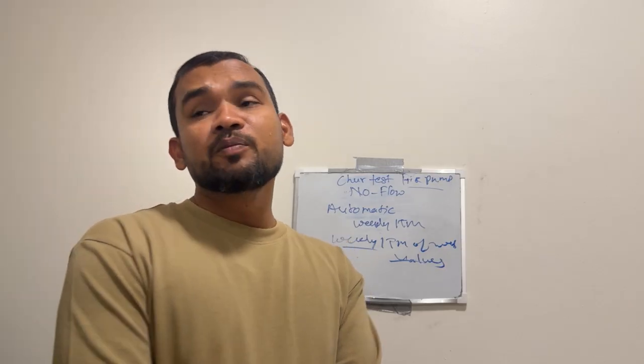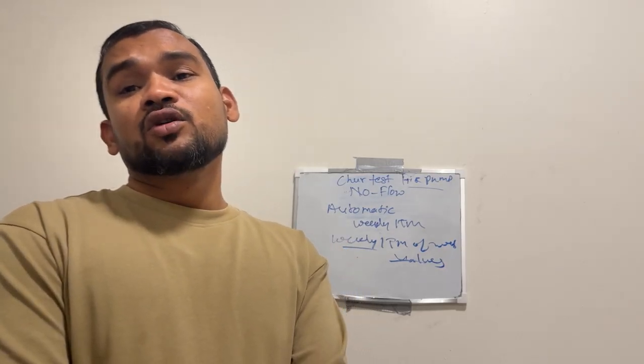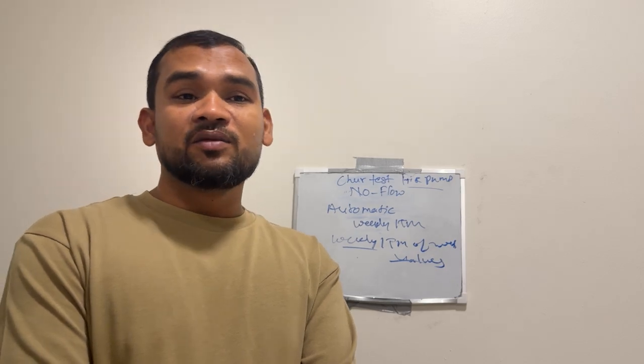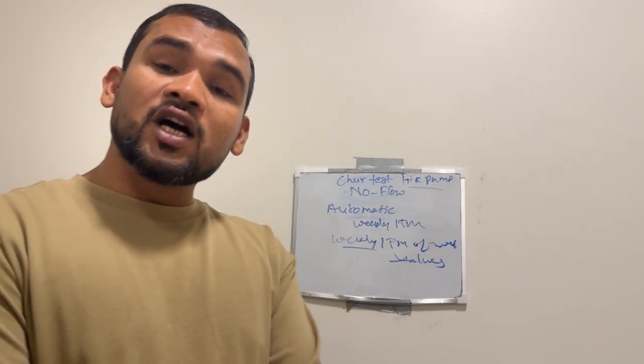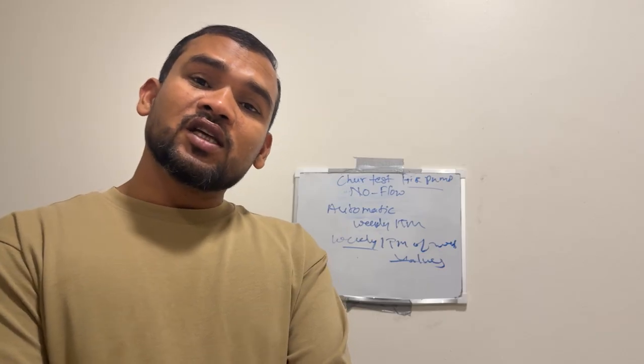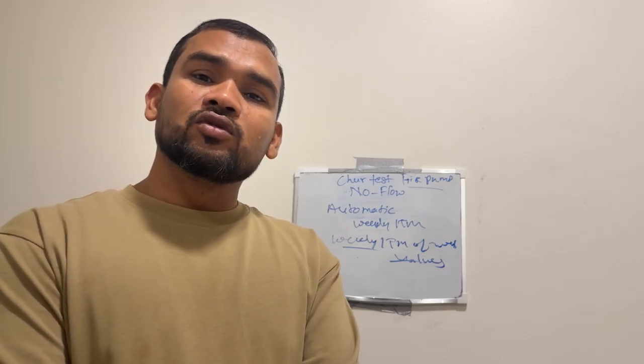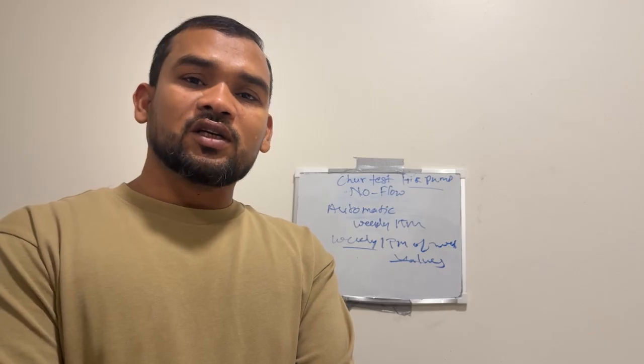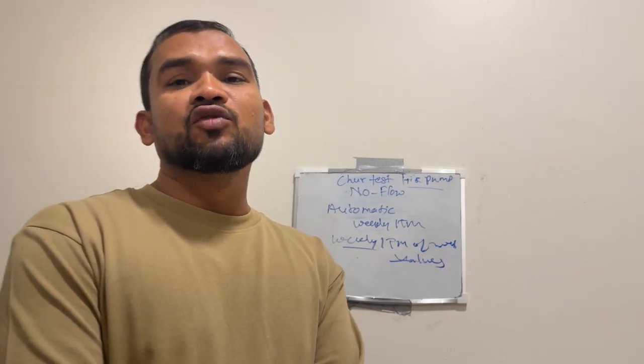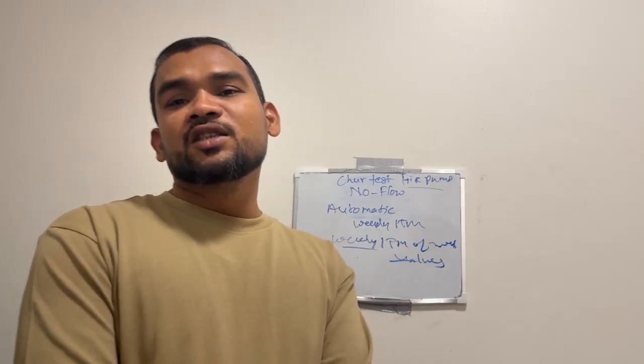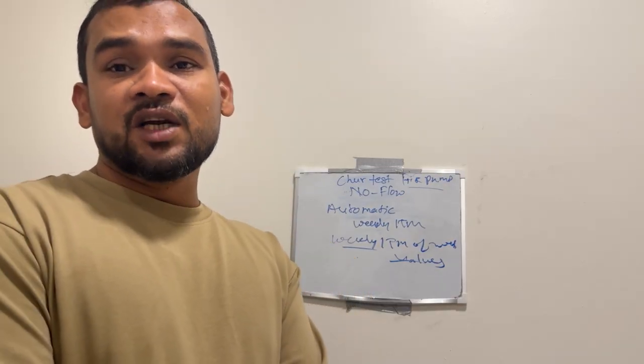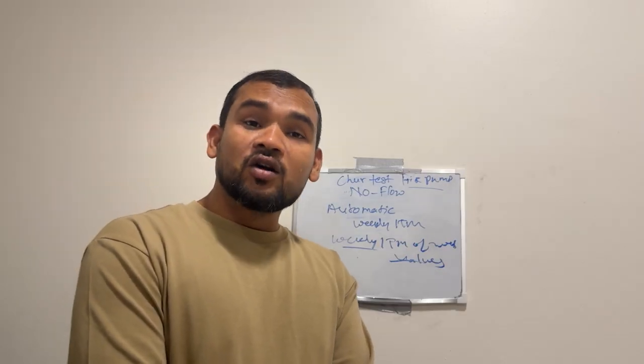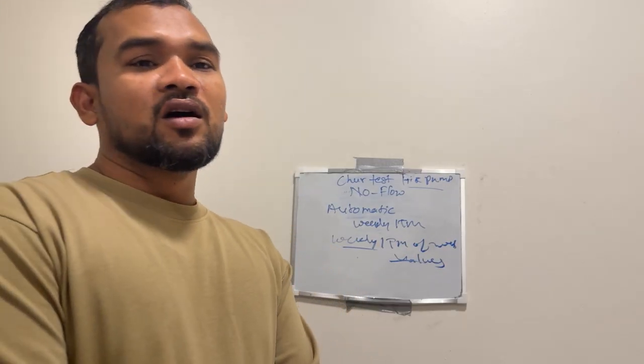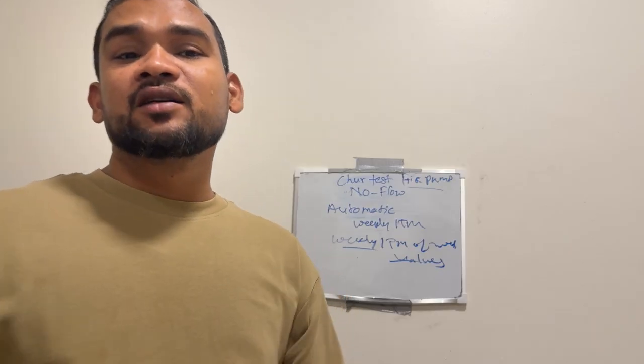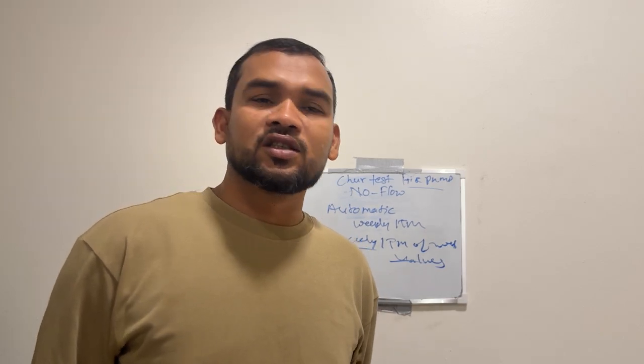And for the measures to protect the facility, we will implement a fire watch on this system. If there is an impairment, we have to assign one fire watcher to check for 24 hours and inform the building owner. We have to increase the fire extinguishers nearby the impairment or deficient system. We have to monitor on a regular basis and mark impairment tags. All of this we do for the protection of the system.